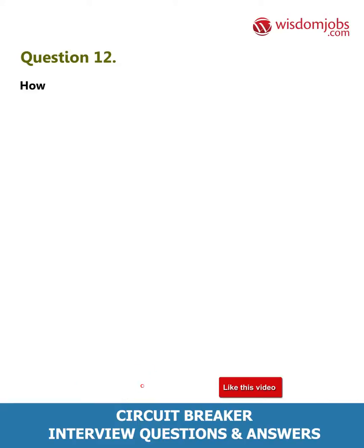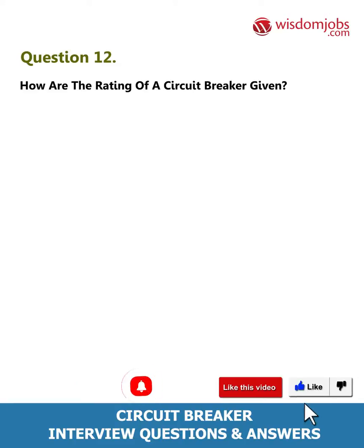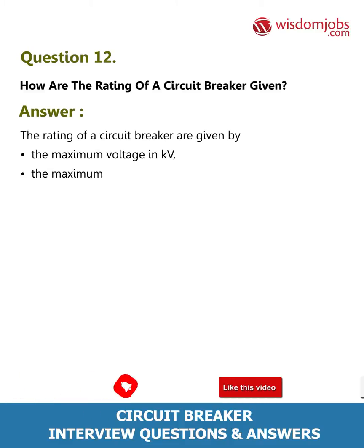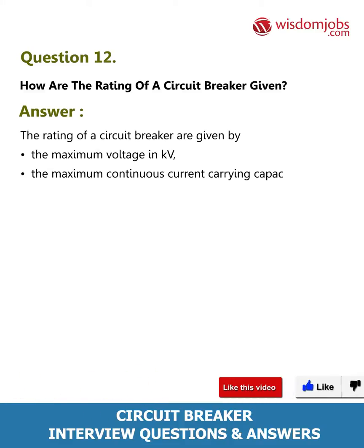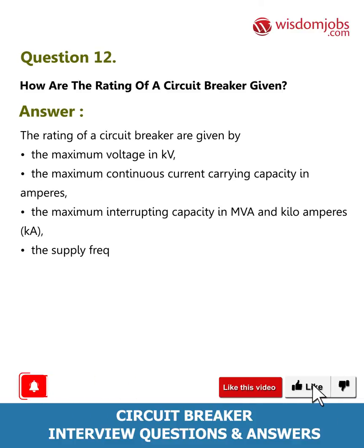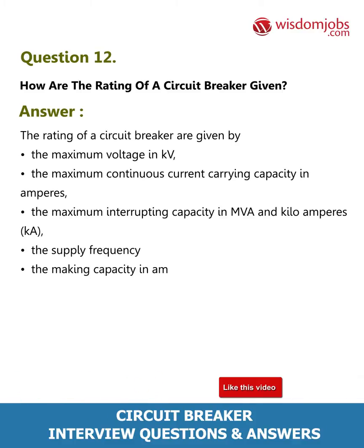Question 12: How are the ratings of a circuit breaker given? Answer: The ratings of a circuit breaker are given by the maximum voltage in kV, the maximum continuous current carrying capacity in amperes, the maximum interrupting capacity in MVA and kiloamperes, the supply frequency, and the making capacity in amperes.